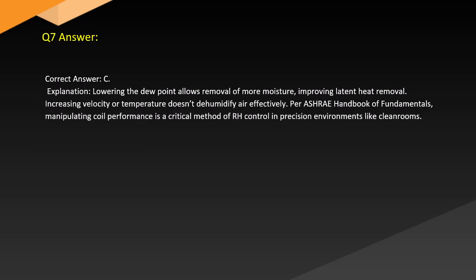Answer. Correct answer: C. Explanation. Lowering the dew point allows removal of more moisture, improving latent heat removal. Increasing velocity or temperature doesn't dehumidify air effectively. Per the ASHRAE Handbook of Fundamentals, manipulating coil performance is a critical method of RH control in precision environments like cleanrooms.